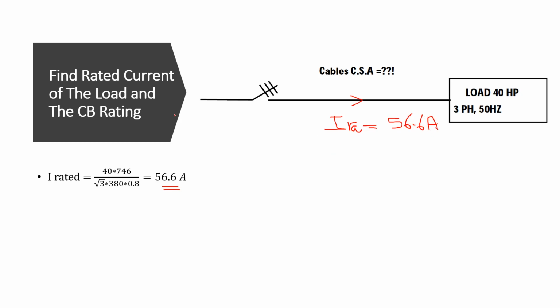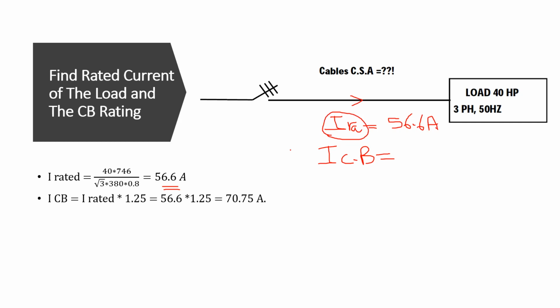Second step, we are going to find the circuit breaker rating. We said before, when we discussed the circuit breakers, that the current of the circuit breaker is equal to the rated current multiplied by a safety factor of 1.25. The rated current multiplied by the safety factor gives us 70.75. If you don't understand this, you can go to the lessons of circuit breakers. So now we have the current of the circuit breaker, which is 70.75 ampere.